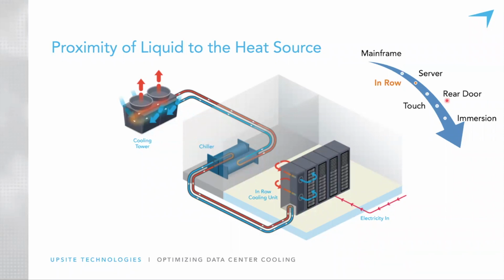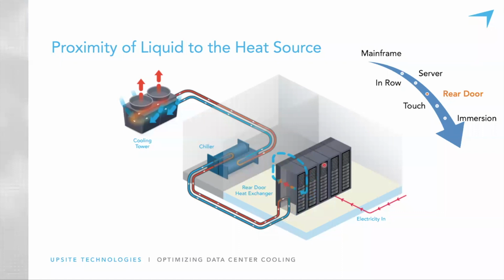And now moving to the next step, to rear door heat exchangers, we're getting now the liquid on the back of each of the cabinets. We have a rear door heat exchanger mounted on the backs of each of the cabinets. And rear door heat exchangers are often referred to as a liquid cooled solution. They do have liquid flowing through them. And so there is liquid cooling occurring in that sense, but it is not truly liquid cooling because liquid is not removing the heat from the source. Air is still removing the heat from the source, and it's only carrying it for a couple of inches before it passes that heat to the liquid flowing through the radiators in the rear door. And then again, through the loops of liquid to pass the heat out to the environment once again.